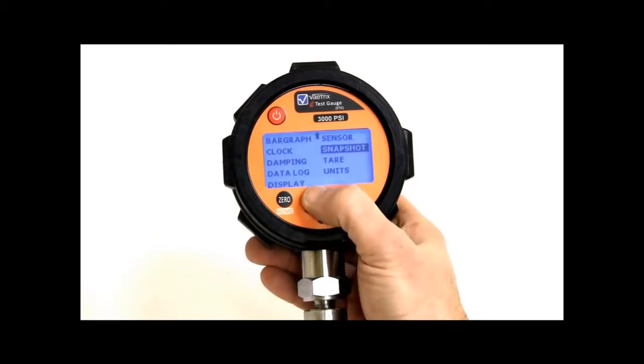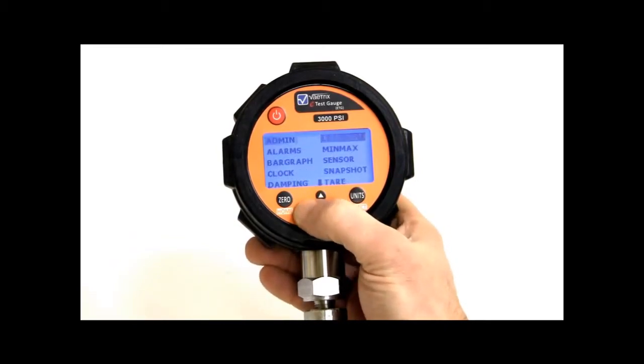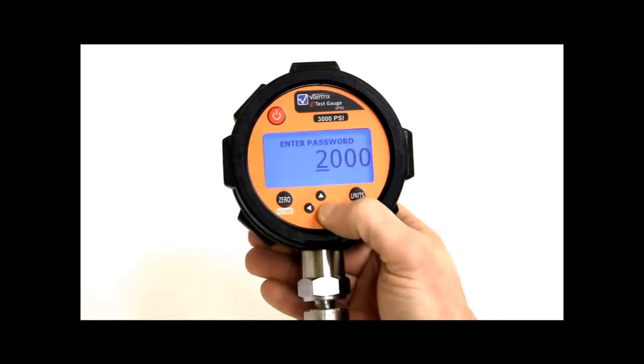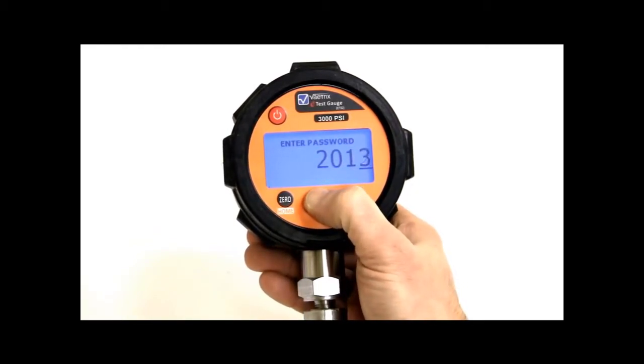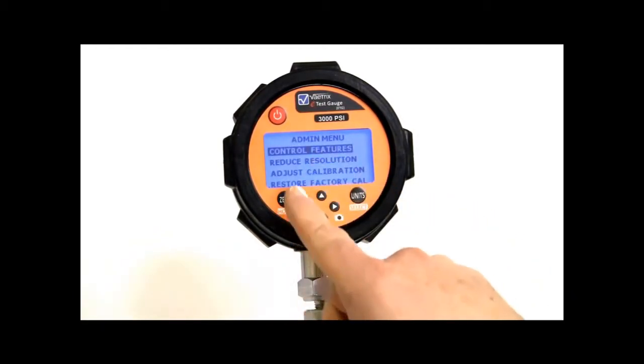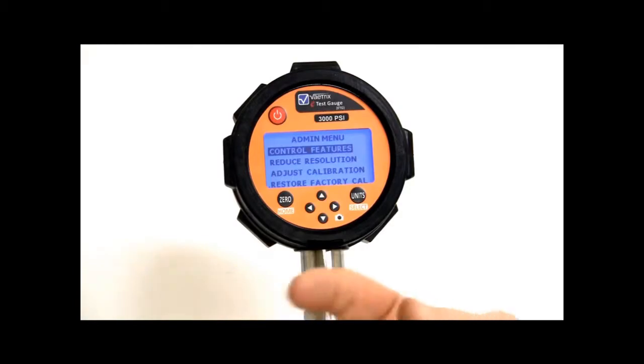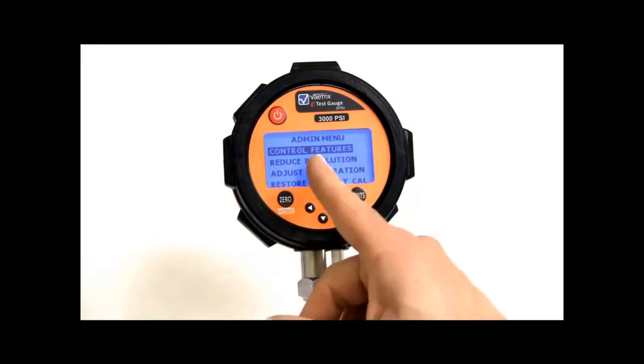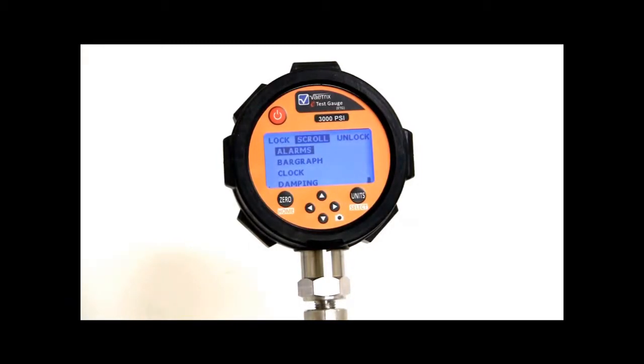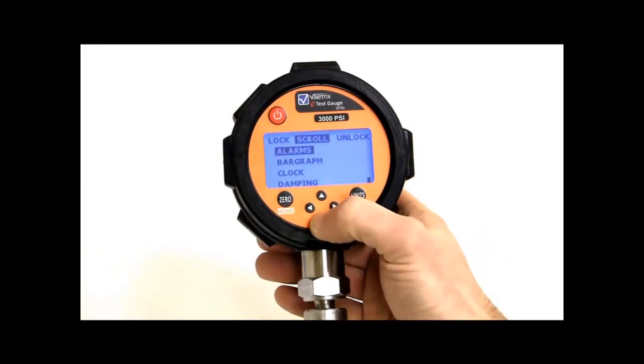Alright, so let's go back to home. Let's dive in to admin. So admin, we give you the capability to lock out certain menus or certain features. And I set the password to 2013. So we'll set that, hit select. So in admin you can restore the factory cal, you can perform a calibration, you can reduce the resolution on the display. Say you wanted to not see the full digits on the display, you can actually adjust that. Now under control features, which is the first one. So I can lock out, it's the same menu that you saw on units. I can lock out particular menus I didn't want people in.